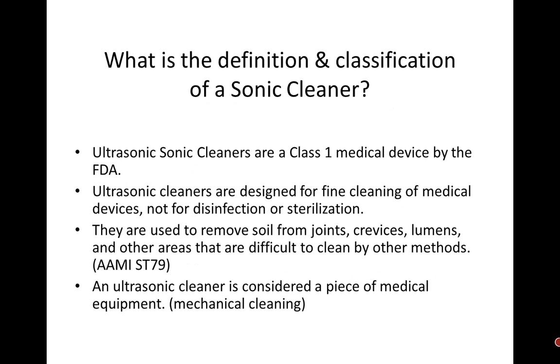They're used to remove soil from joints, crevices, lumens, and other areas that are difficult to clean, where you might not be able to get it by regular brushing and flushing and so on. It's there to really do some of that fine, deep cleaning you need. An ultrasonic cleaner is considered a piece of medical equipment within your facility. Your biomed department is tracking it. It has a tag, and that's very important when we start to connect the dots, how you use it in your department and how you should track it.